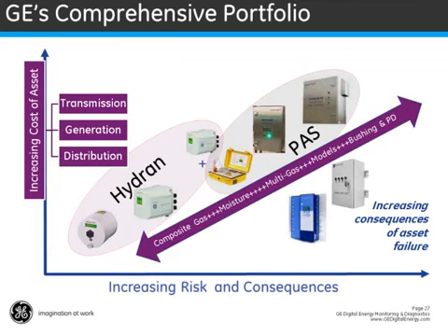From the very basic composite single gas hydrogen technology to the more advanced multi-gas photoacoustic technology, today GE's monitoring and diagnostic product portfolio offers a wide range of integrated online solutions to assist users to better monitor and manage transformers on their electrical grid.